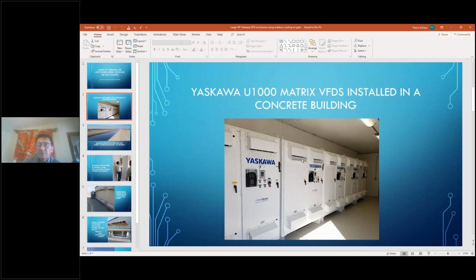The fans have to be sized up a little bit because they're blowing out hot air instead of blowing in cool air. But that's a small compromise to achieve higher performance of this design versus fans on the input. Again, we're balancing thermal environment with dirt environment, particulate ingress, and moisture ingress. In this controlled room, this is a concrete preformed building. We don't have a lot of issues with dirt and moisture, but we definitely have some thermal.